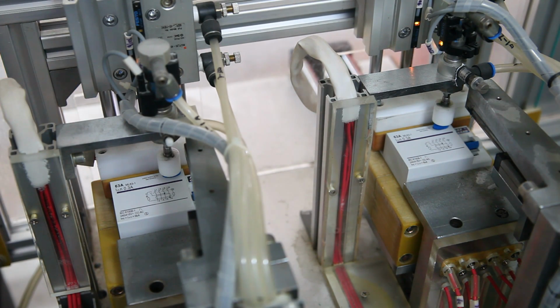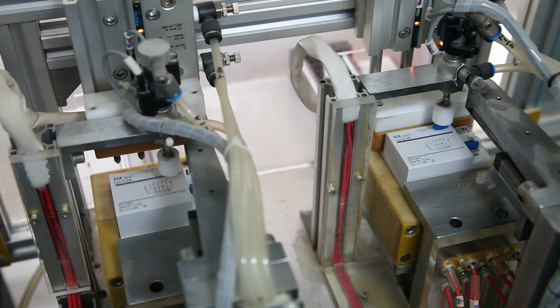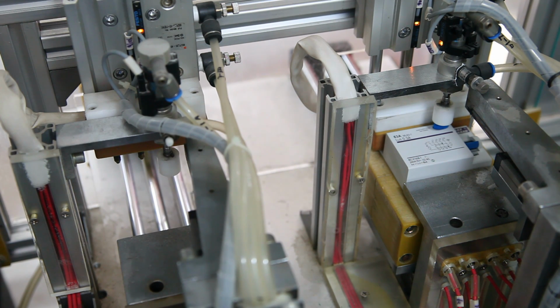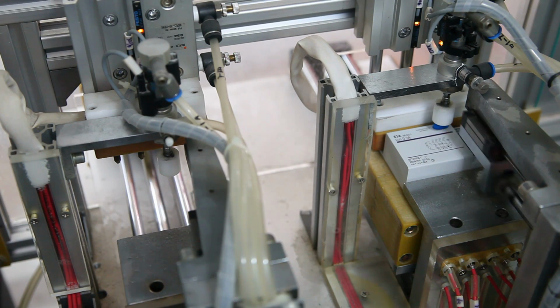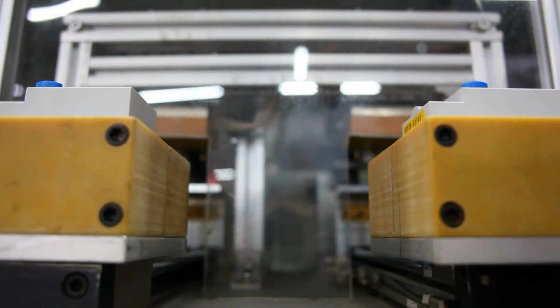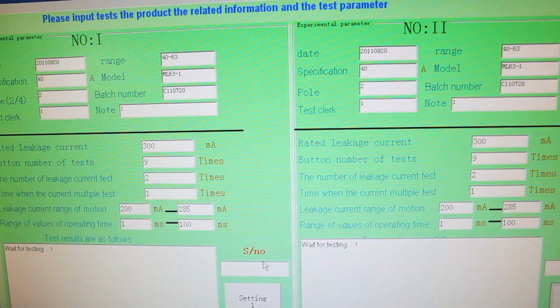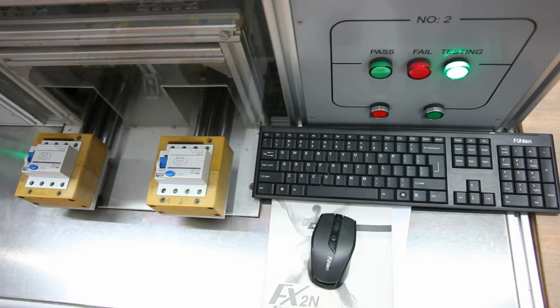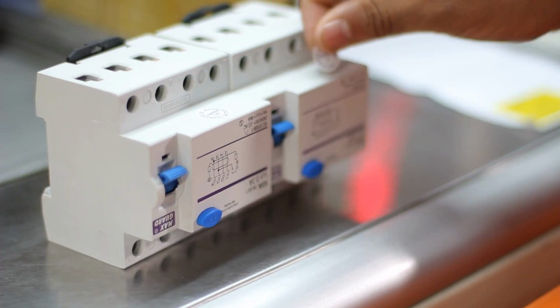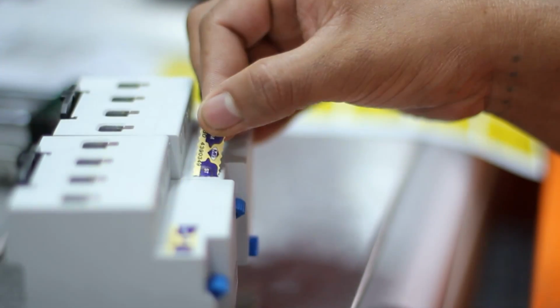The RCCB test button is depressed automatically 9 times in succession, followed sequentially by 2 times leakage current measurement, preset between 65% to 95% sensitivity current. And finally, trip-free verification with a measurement of the tripping time. The criteria for compliance is as mentioned above. All the results will be automatically displayed on the monitor screen, and a green box appears to indicate qualified and a red box for unqualified.